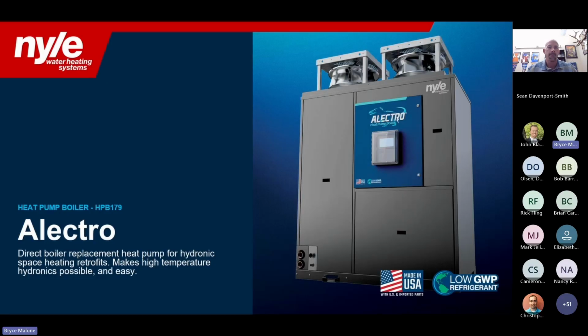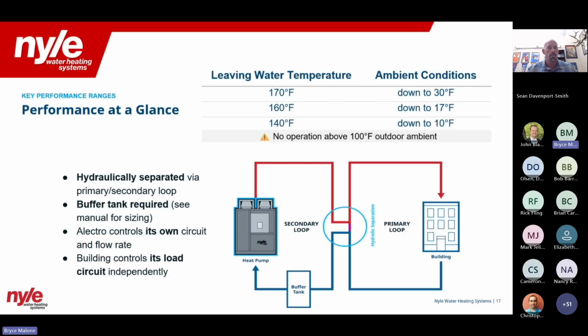And then we transition now into the air source side and our purely, specifically designed for space heating heat pump boiler application. The only one of its kind. This is for high temperature boiler replacement. So the Alectro, which we launched about 6 months ago, is your drop-in boiler replacement. So this unit will deliver 170-degree temperatures.